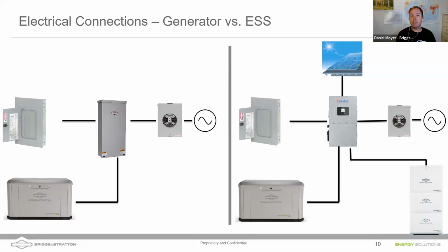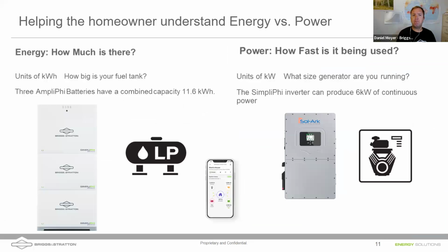If the Sol-Ark detects that the energy storage batteries are starting to be drained, we can go ahead and program certain set points. We're going to show you how to set those points up here in a minute to start up that generator, charge up the batteries, support the home loads, and then shut that generator off once we've reached a certain threshold on the battery level. So very similar, but a little bit different. I just wanted to demonstrate that here on this slide.